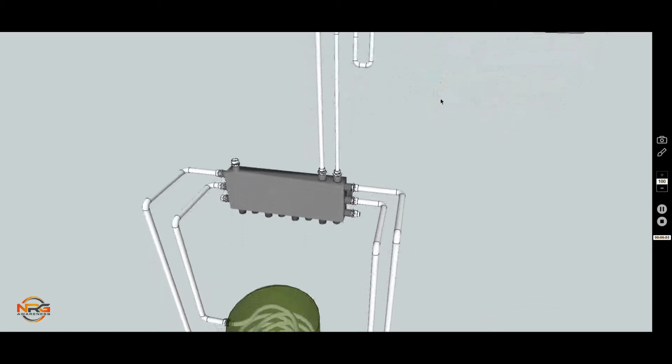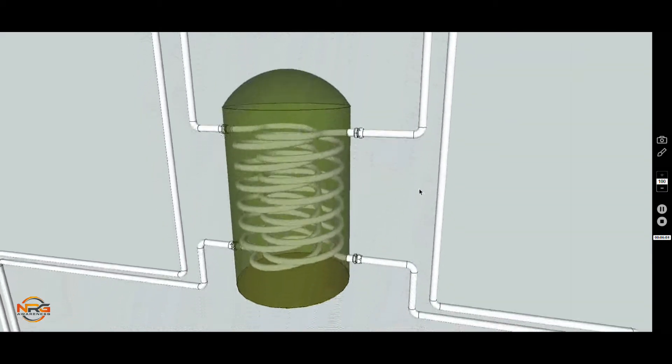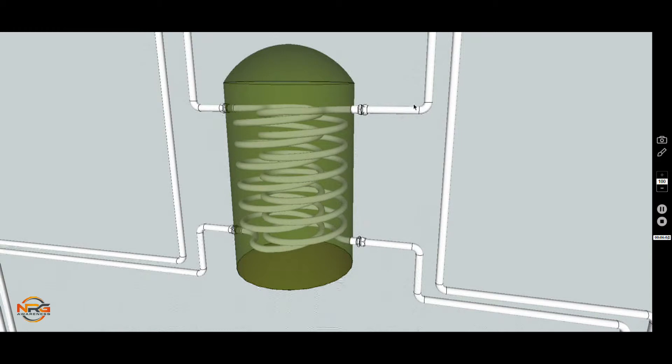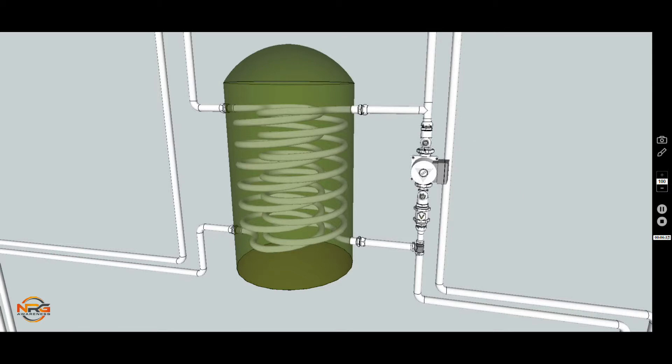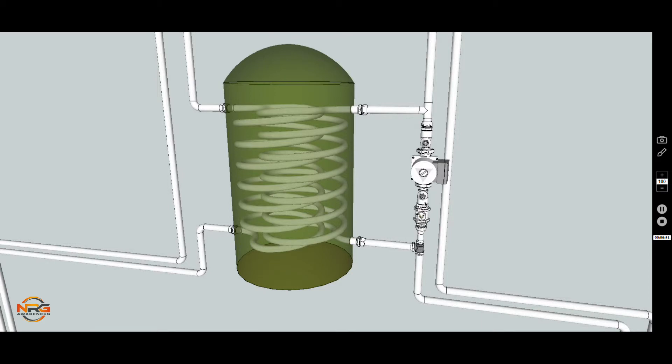Now we look at the dual coil cylinder and just suppose the stove on the right hand side is a bit more powerful than what primaries might be able to take away all of the heat, because the stove might be too big or heat potential too big. So instead of having just a non-pumped circuit, we could introduce an injector T along with a pump. What this would mean: if the pump is not running, the hot water would be at this point. The non-return valve would stop any inadvertent water circuit slipping by the cylinder and just drifting down, because the water wouldn't have the potential to open this non-return valve. So it would carry on as before, deliver its heat to the coil, and then carry on back.